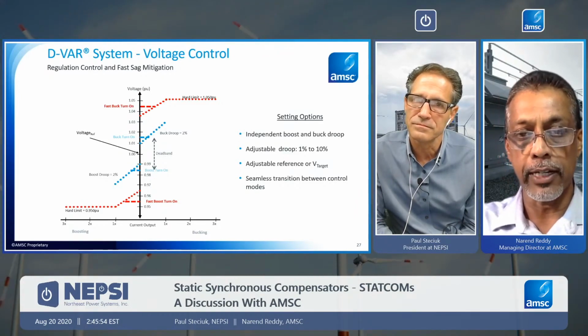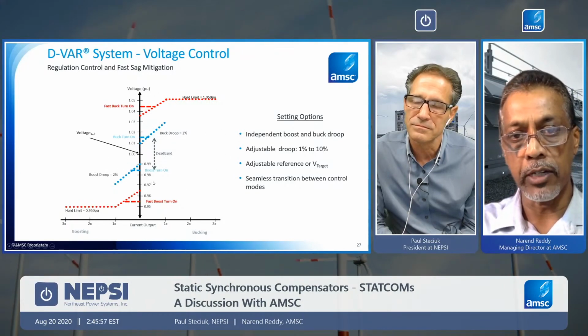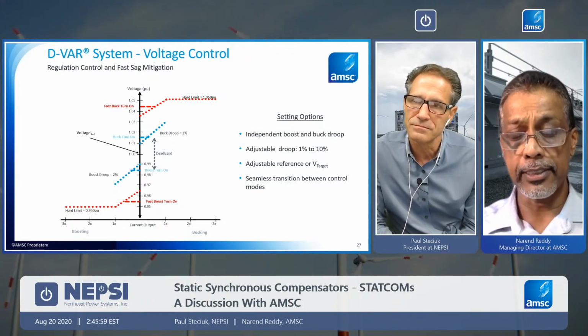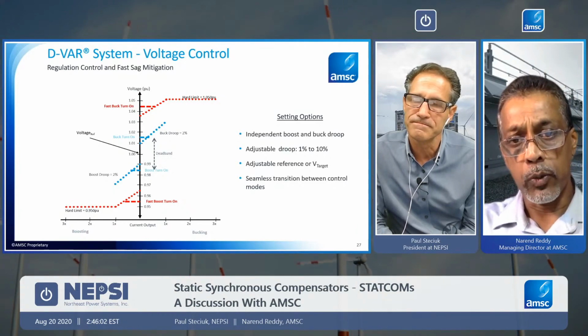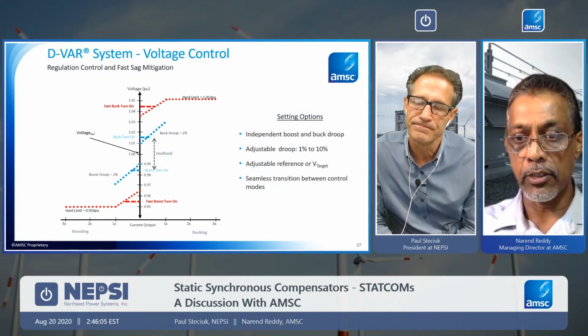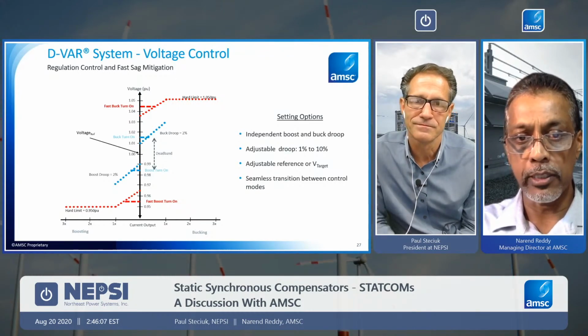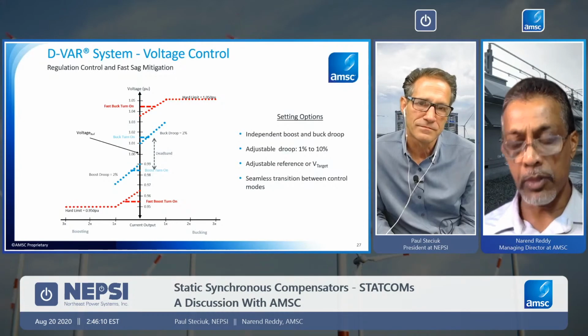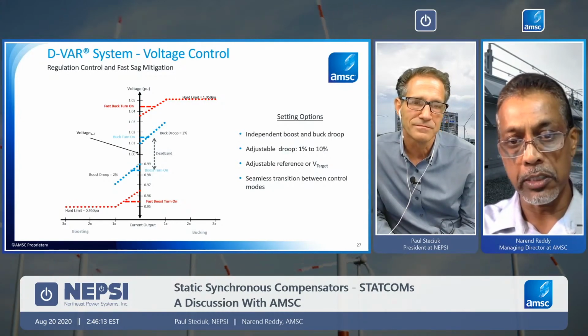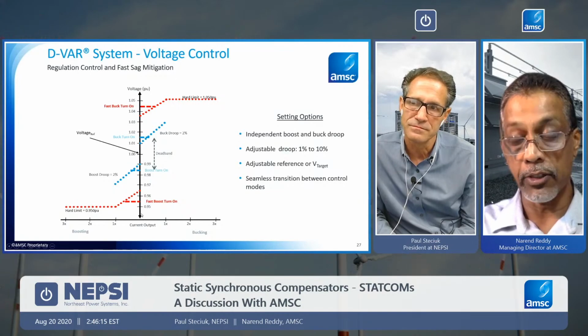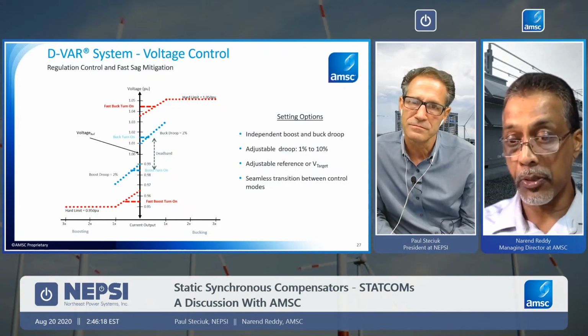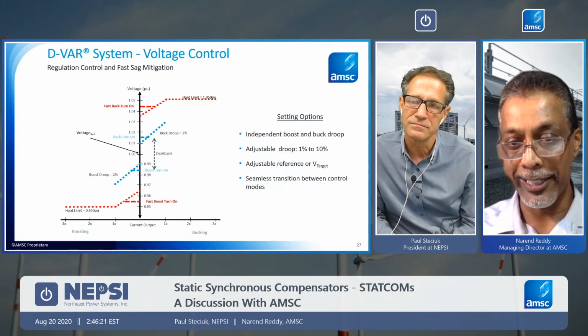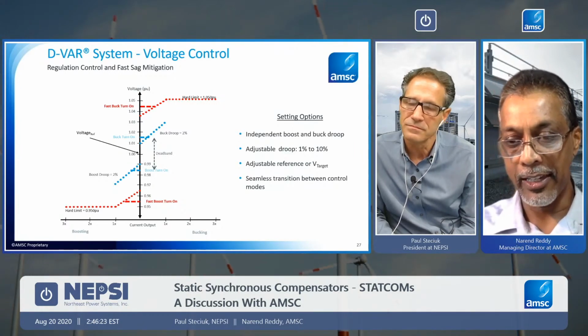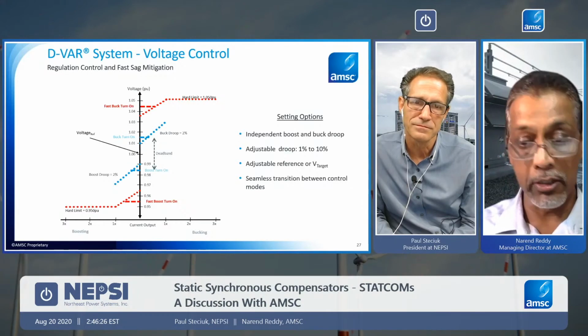So there's a different set of gains and a different set of parameters that are utilized for what we call the steady-state regulation. But when the system transitions or detects a fault situation, such as a single phase fault or a big deviation in voltage that violates these regions out here, for the red to come on, now that response is super aggressive. It is a matter of cycles, and within a few cycles you need to be active. You need to get out to as much current as possible.